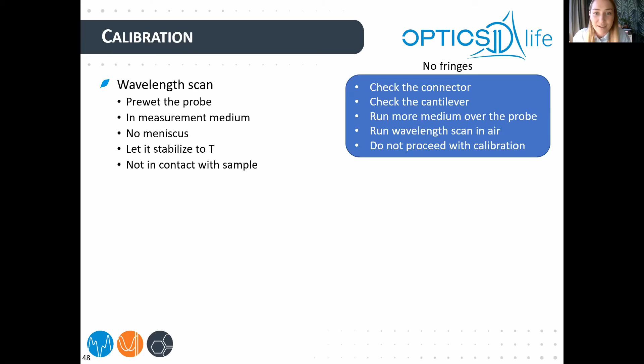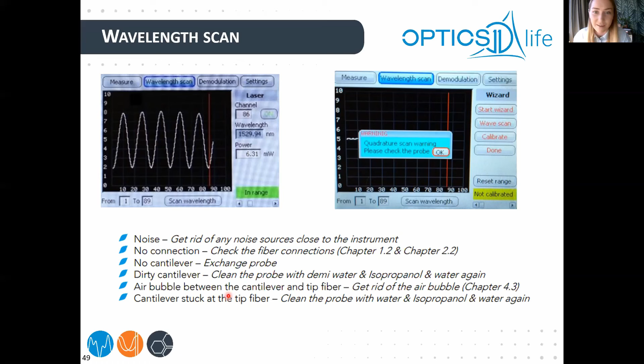And I have here an example of how the wavelength scan should look. If there's no good result, you also get a message that the scan has failed and please repeat. There could be many different things that are wrong. I have them listed here, and you can find them in the manual. It could be anything, so we have to try to find where the issue is.